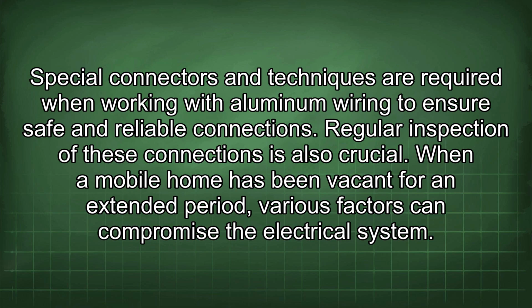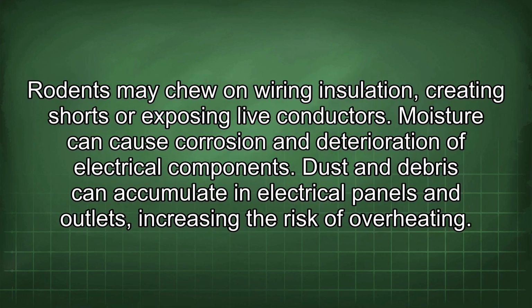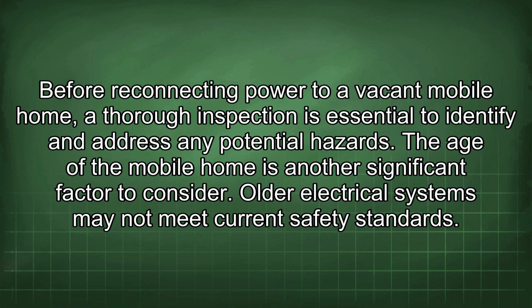When a mobile home has been vacant for an extended period, various factors can compromise the electrical system. Rodents may chew on wiring insulation, creating shorts or exposing live conductors. Moisture can cause corrosion and deterioration of electrical components. Dust and debris can accumulate in electrical panels and outlets, increasing the risk of overheating. Before reconnecting power to a vacant mobile home, a thorough inspection is essential to identify and address any potential hazards.